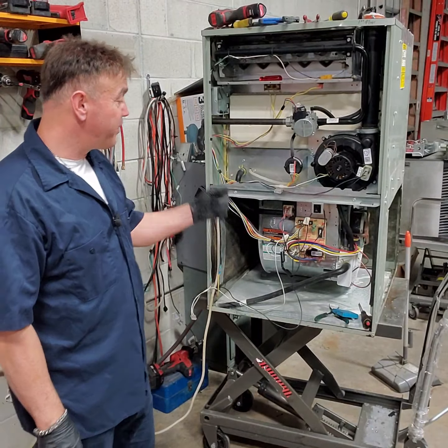So if you want a higher speed on furnace mode, you can change it. Basically red is low—usually red is low almost every time. Black is high. White is common. Sometimes you have medium-low and medium-high, so there will be two colors—blue could be low medium, and yellow could be high medium. Sometimes you only have red and white plus yellow, which is just a medium, with no high or low medium, just one medium.